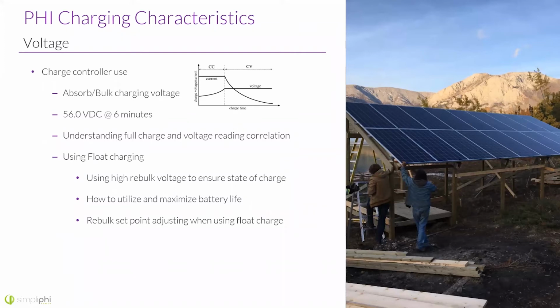Okay, a little bit about voltage and charging. We're going to start with charge controllers. If we are using a charge controller and DC coupled, we're going to use absorb and bulk, of course. That's 56 volts DC at 6 minutes. For the most part, that's the bulk of the charge when it comes to lithium batteries. About 90% of the charge happens in that stage. So we don't always need float, but when it comes to a charge controller, if you're charging from a PV array, go for it. Use a float voltage. 54.0 is where we recommend it.